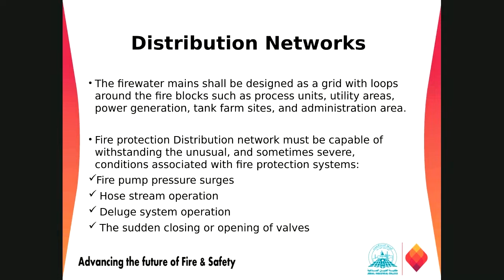So when you are reviewing the plan for the fire protection system, it should be capable of withstanding the usual load, unusual load, and sometimes severe load coming from the fire protection system from time to time. Like the fire pump pressure surges, when suddenly pressure goes higher in the fire protection system, or maybe a deluge valve is activated. When a deluge valve is activated, water suddenly starts flowing, and at some point there will be a peak in the pressure. So that pressure we have to keep in mind.